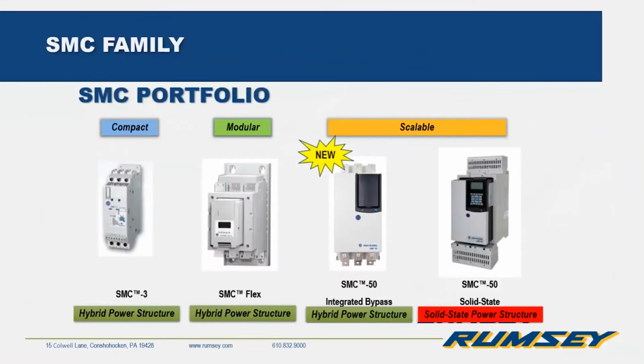And the soft starters. So here's an overview of the soft start family. So we have the SMC3, which is your basic soft start, up to 37 amps. It's only 45 millimeters. So that's smallest in the industry. But it's a basic soft start. It is configured with dip switches and a rotary dial. It does have an internal bypass contactor. We have the SMC Flex, kind of middle of the road. That comes with the HIM module mounted on it, and that as well has an internal bypass contactor.